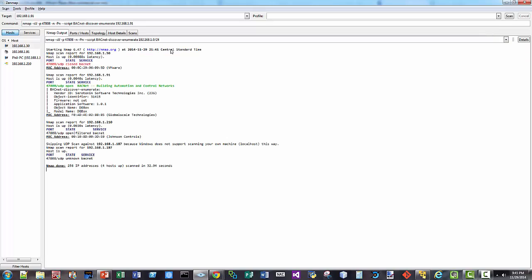So what happens when I do that is I pick up two systems. Alright, see, I've got one right here. And I've got a second one. I've actually got two BASs attached to my network right now. So you can imagine if you've got a large hospital network, you can use this to find all the building automation systems because quite often they aren't documented where they are. And people don't really know what's sitting. You can have BACnet IP lighting sensors, BACnet IP power sensors. You can have a bunch of BACnet IP devices and not know where they are. And those are typically embedded machines, and those can be compromised. So it's a good way to audit your network. And it's something that traditional network audits don't look for.